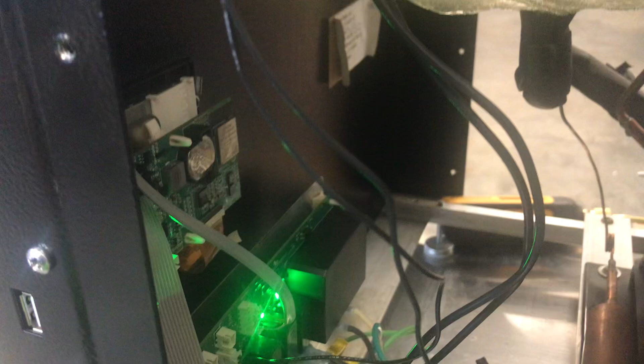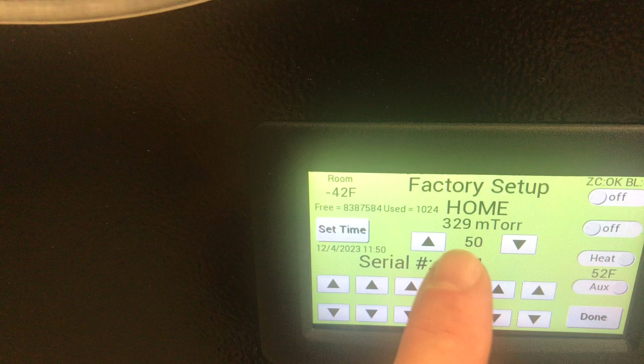I put in a new USB board and a new relay control board. Put in a new epoxy harness, and then replace the pigtail on the back of the rack, so it's all the new stuff with the nice Deutsch plugs. And you can see the reason for the video here is the machine comes from the factory offset to 50. This is the default setting, and it's showing 329 mTorr, which is great.